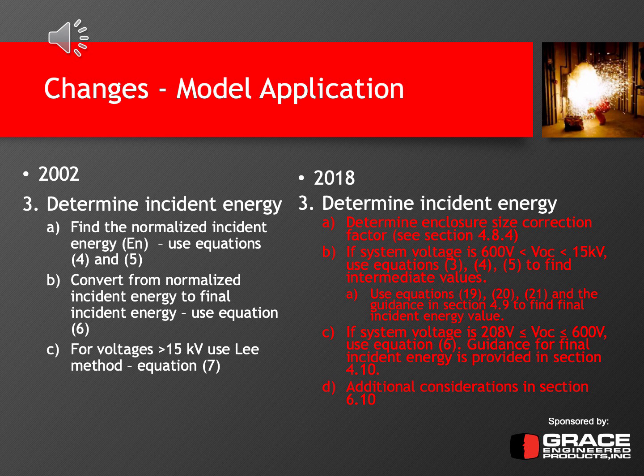In 2018, the next step you need to do is determine the enclosure size correction factor. So this is where your enclosure size really comes into play. Back when you determined the arcing current, it was the electrode configuration, but now it's the enclosure size, because there are different incident energies that are based on the enclosure size.